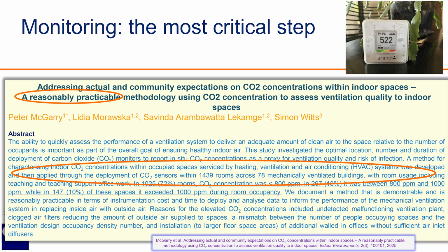So what the study showed was that 85% of the spaces were fine in terms of meeting the proposed standard, which I mentioned a moment ago. In the 15% which were not meeting it, it was also easy to say that there were issues like broken filters, exceeded occupancy, or something like this. So this is a reasonably practical methodology, and doing this en masse in every building is absolutely possible, easy and not expensive right now.